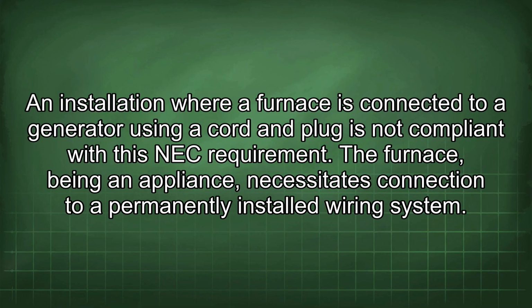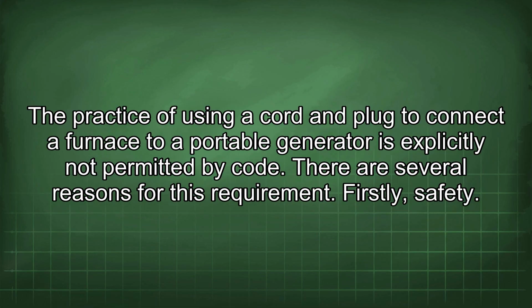An installation where a furnace is connected to a generator using a cord and plug is not compliant with this NEC requirement. The furnace, being an appliance, necessitates connection to a permanently installed wiring system. The practice of using a cord and plug to connect a furnace to a portable generator is explicitly not permitted by code. There are several reasons for this requirement.